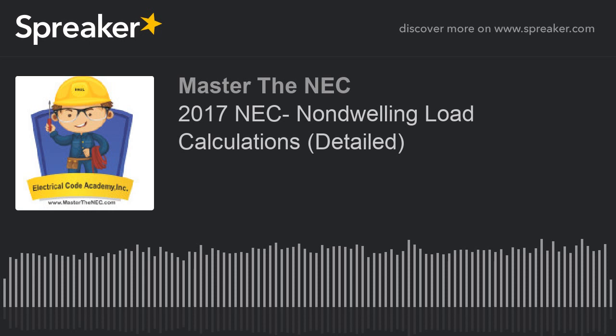So now I add the two figures together. The first one was 20, and the second one was 30. So my total VA for these patient rooms applying this demand factor is 50,000 VA. And I can plug that in as my general lighting demand factor.